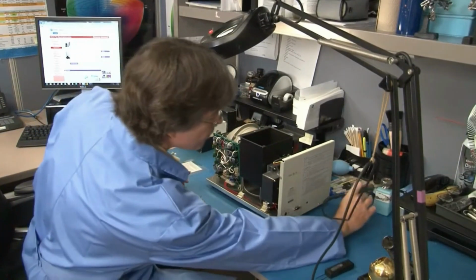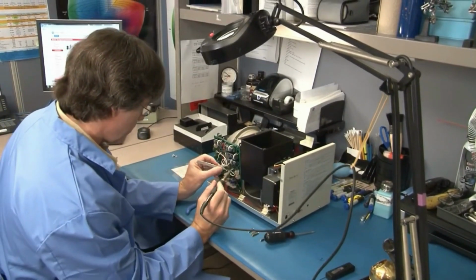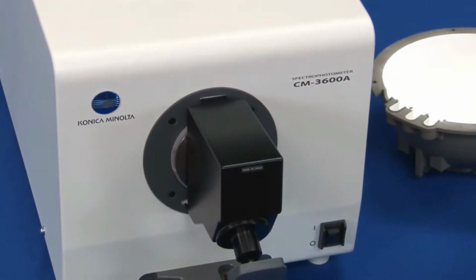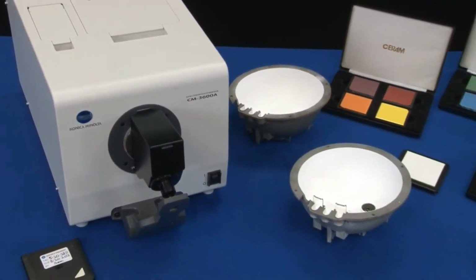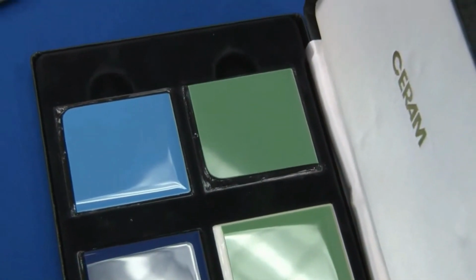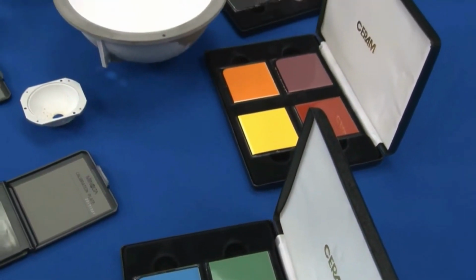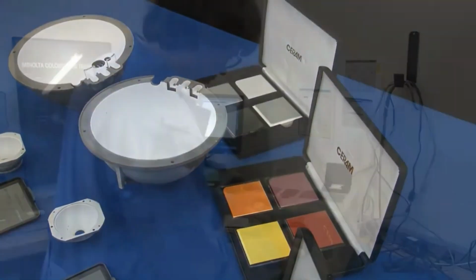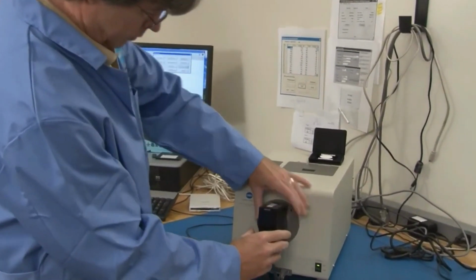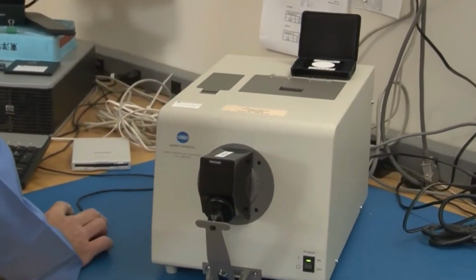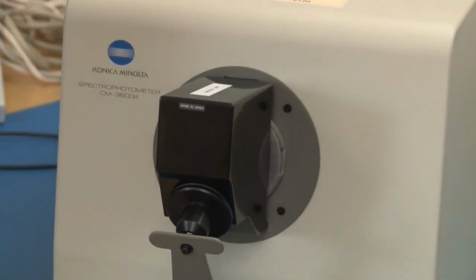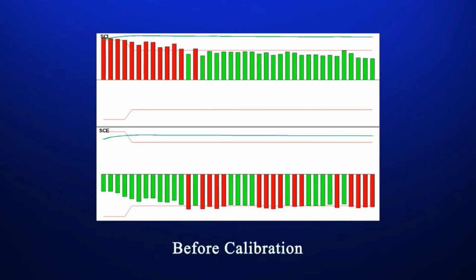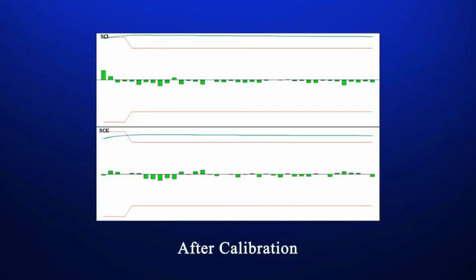To ensure instruments will function correctly over time, it's necessary that all color measurement instruments receive factory calibration on an annual basis. To demonstrate the value of annual calibration, we will be using a CM3600A spectrophotometer as our sample instrument. As part of our inspection process, 14 color standards certified by Konica Minolta and traceable to national standards are used to determine the performance of the instrument. Before service is performed in our state-of-the-art laboratory in Ramsey, New Jersey, an evaluation of the instrument and its condition is completed by a trained service engineer. Seen here are the results of the inspection process. As a result of annual calibration, the instrument is brought within factory specifications. Konica Minolta's service facility is dedicated to providing quality, performance, and value.